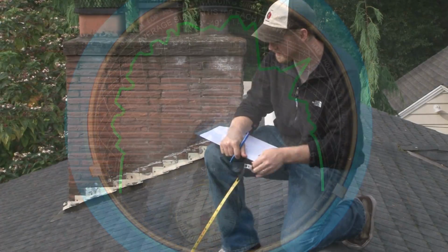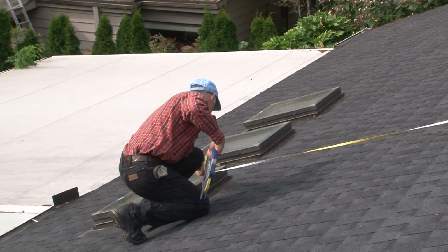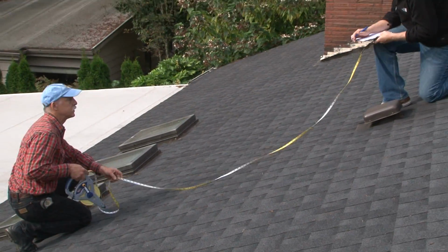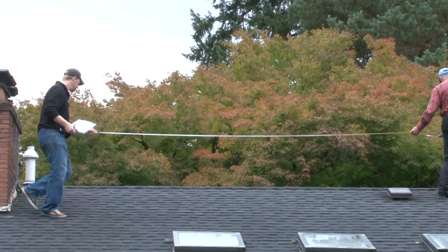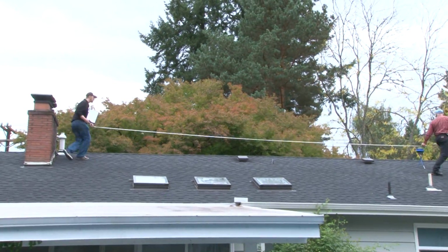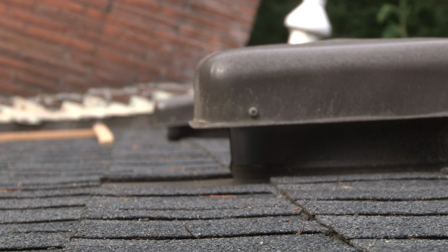With the photo in hand, the technician identifies the areas of the chart that will be shaded and hand calculates the solar resource fraction. Next, the technician will measure the available roof area in order to calculate the number of panels that can fit on the roof, and will identify any roof penetrations like vents and chimneys. Some penetrations like sewage vents can be moved to open up a greater area for the panels to go down. Another consideration is the age of the roofing surface. Some incentive providers require 10 to 15 years of remaining life expectancy for your roof material.